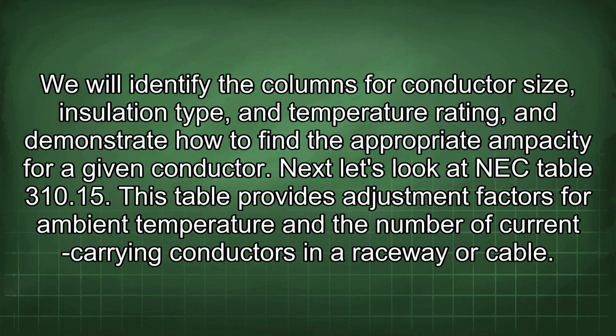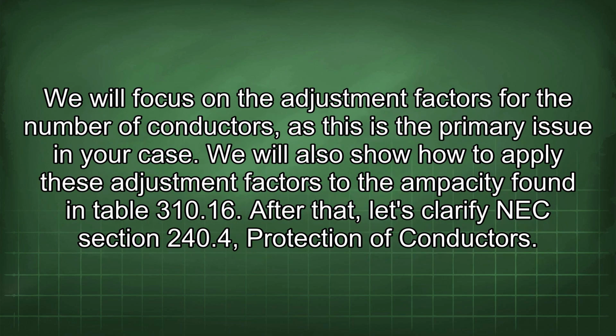Next, let's look at NEC Table 310.15. This table provides adjustment factors for ambient temperature and the number of current carrying conductors in a raceway or cable. We will focus on the adjustment factors for the number of conductors, as this is the primary issue in your case. We will also show how to apply these adjustment factors to the ampacity found in Table 310.16.